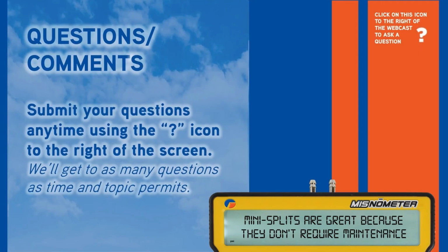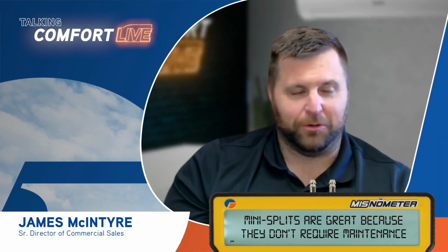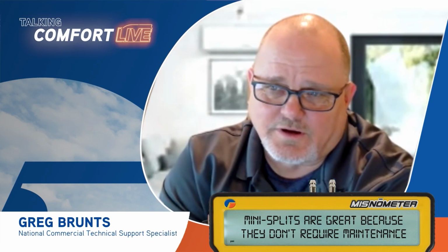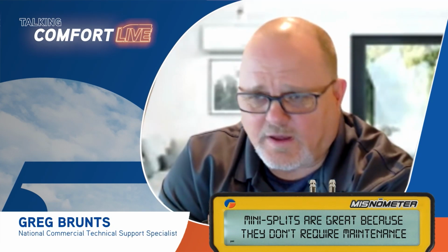We see a lot, in the fall, nothing's been cleaned all year. And then all of a sudden they start tripping out on an error code, like an H5 or something. That's the first thing we say: have you checked the coil? Well, it ran fine all summer. Probably didn't. These machines do a great job of protecting themselves without shutting down.